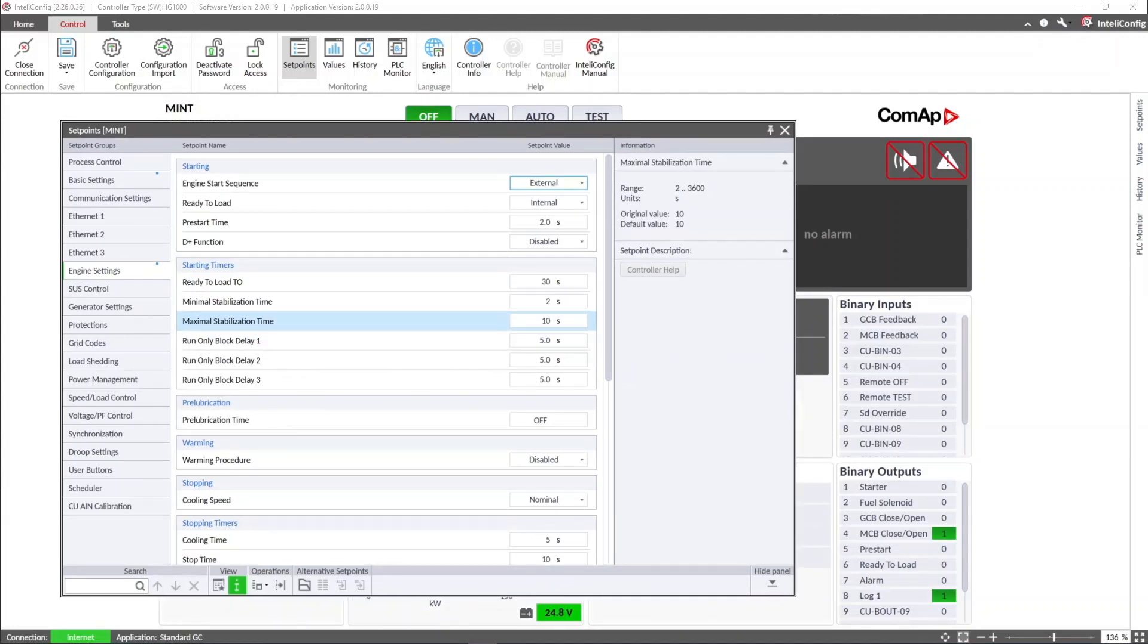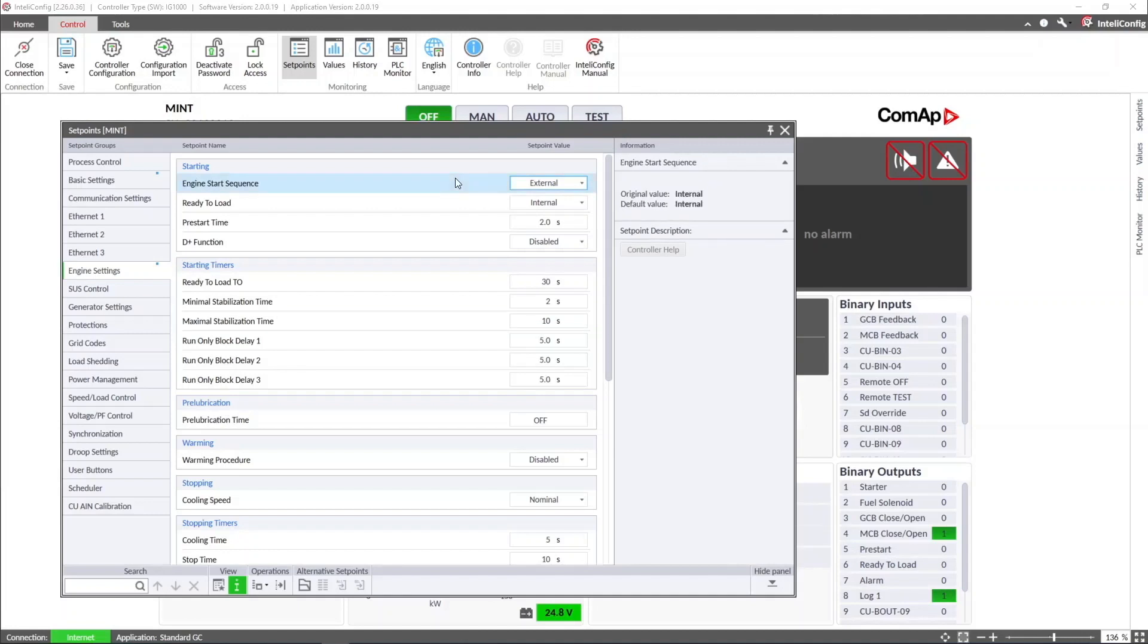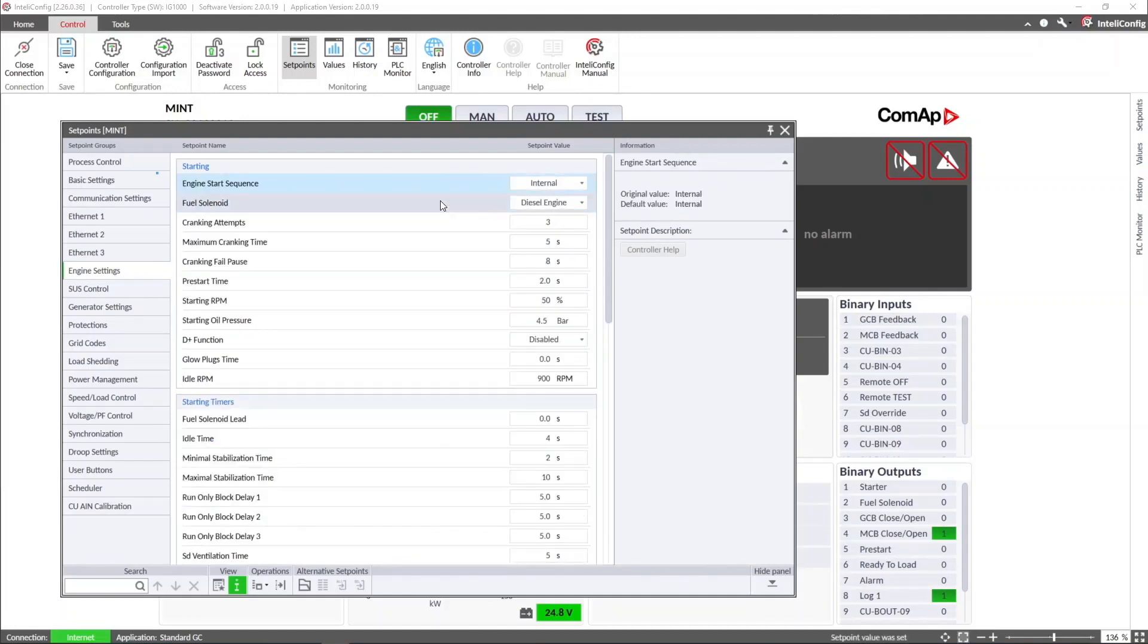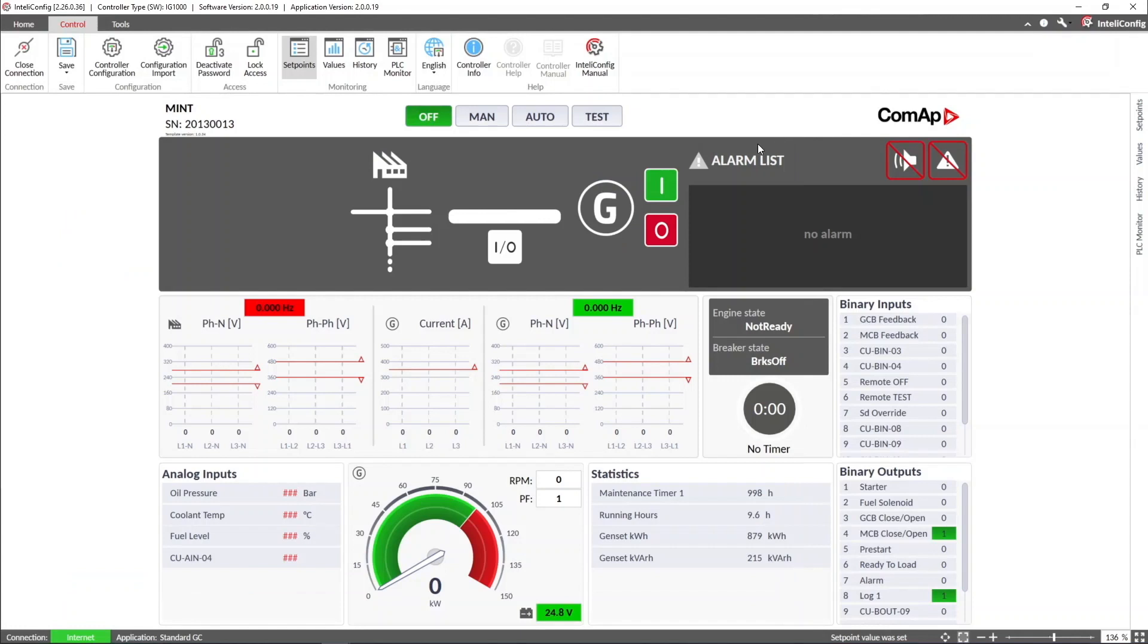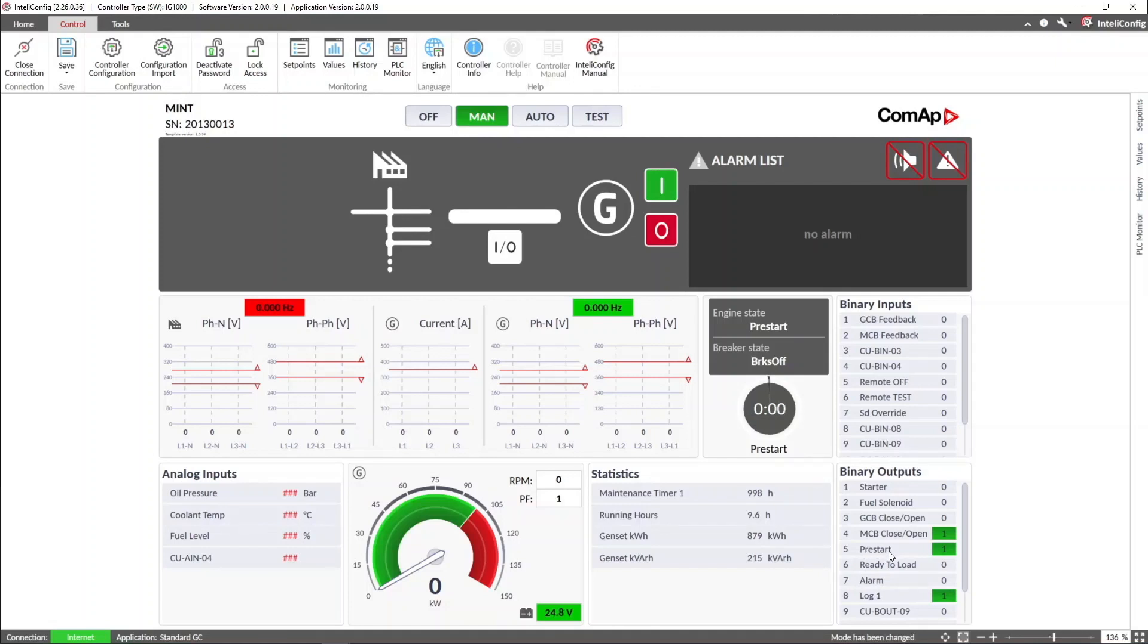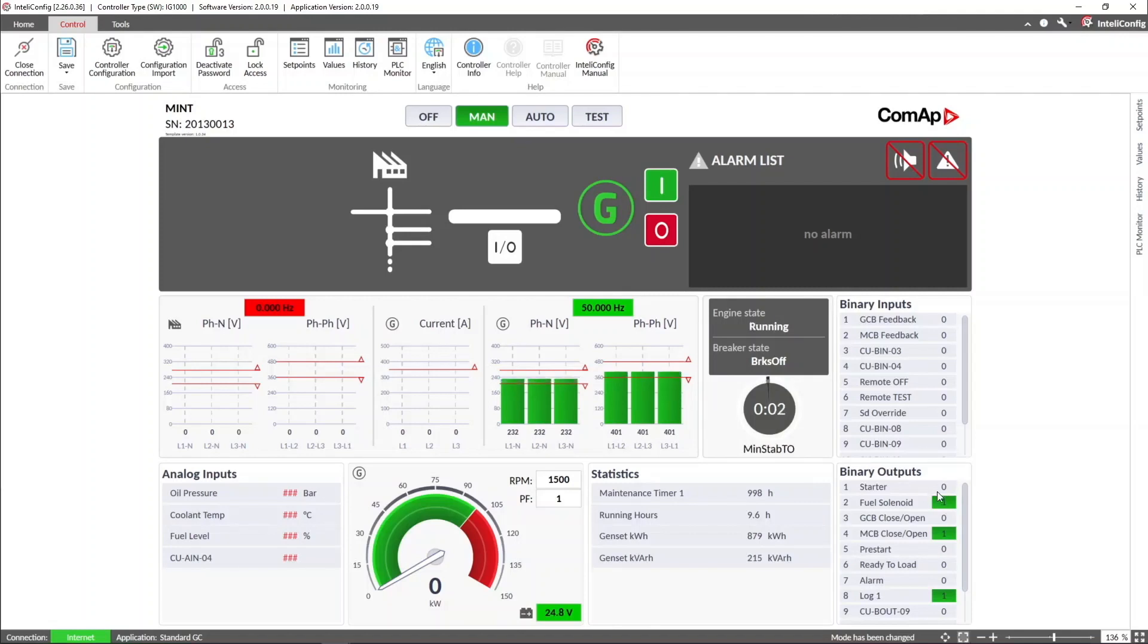Let's check the differences between the two options for the engine start sequence. With the option internal, we can set the maximum cranking attempts, maximum cranking time, and the cranking fail pause. Here we can see how when we press start with the controller in manual mode, the prestart output gets active, then the starter gets active during a short time while the genset starts, together with the fuel solenoid output, which remains active.